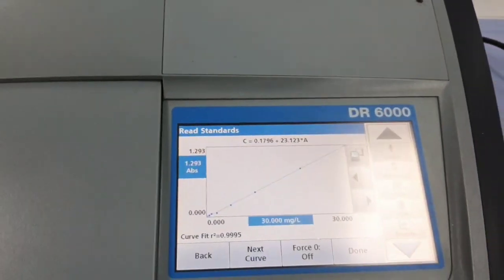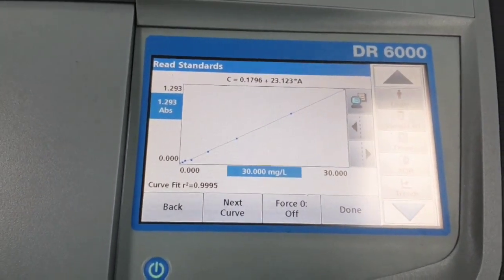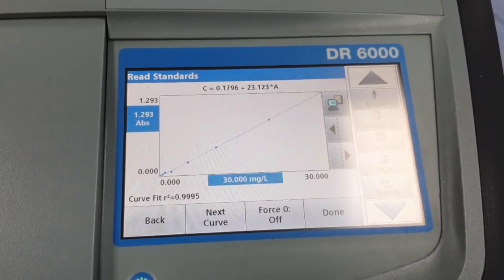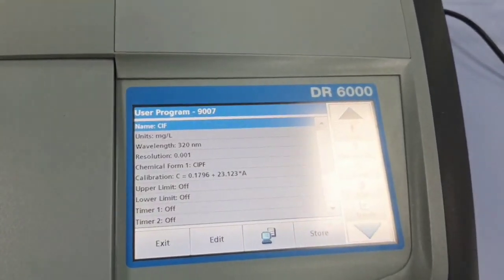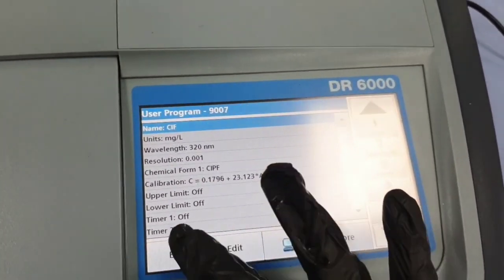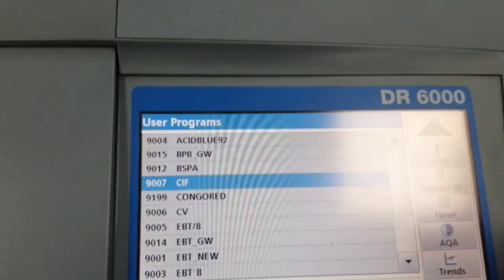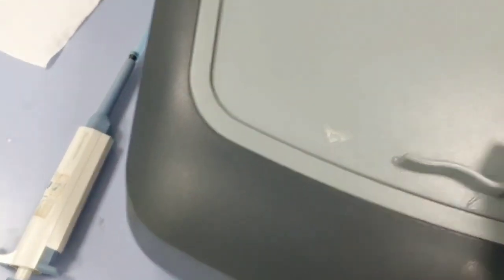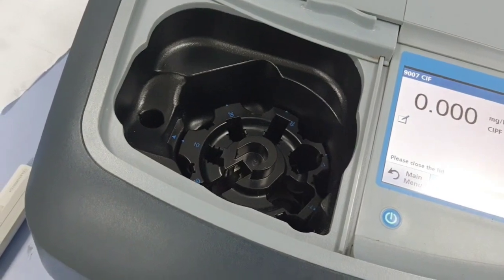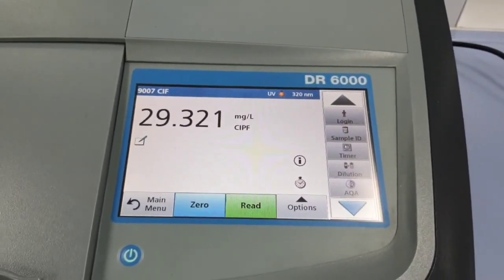Now we will check the calibration. You can see the calibration is 0.9995, so it's almost equal to 1. So our calibration is okay. We'll store this. Okay, now it's stored. Now we come out of this window, and you can see it is stored here. For measurement, it says start, and we can use this as unknown. We'll press 0, so it's 0, and then we check the 30 standard. It's almost equal to 30, so our calibration is perfectly okay.